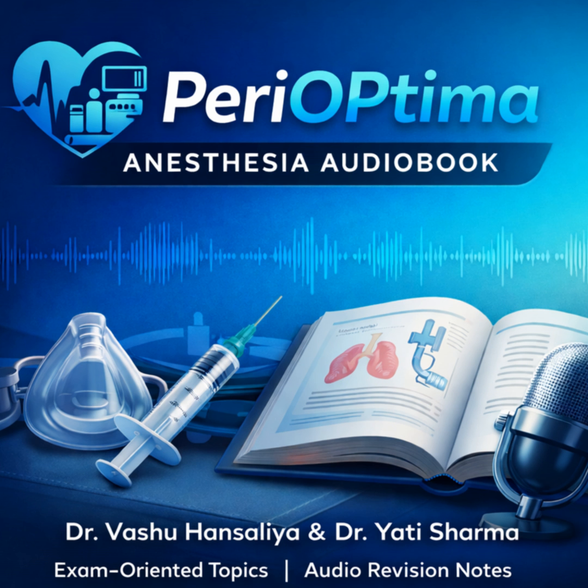And for my expensive, delicate fiber optic laryngoscope. There you have options. Glutaraldehyde or OPA for high-level disinfection, maybe sterilization if you have 10 hours, or the more modern choice, low-temperature plasma sterilization. Tell me about plasma. That sounds like something out of science fiction.